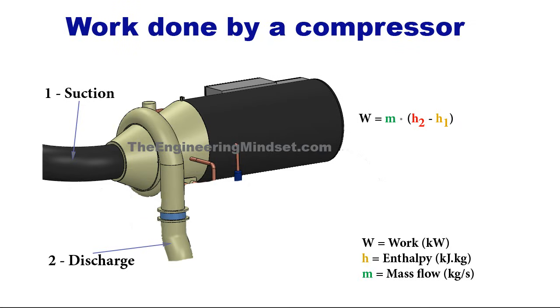So the amount of energy used is the mass flow rate multiplied by the change in enthalpy from H1 to H2, between the suction and discharge line. So let's say the refrigerant flow rate is 3 kilograms per second. That's the mass flow rate. You can see it's color coded in green there as well. So per second there's 3 kilograms of refrigerant passing through. And the difference in enthalpy, the discharge is 420 kilojoules per kilogram, and the inlet is 396 kilojoules per kilogram.